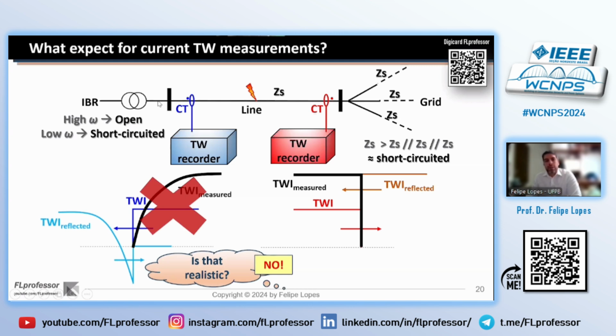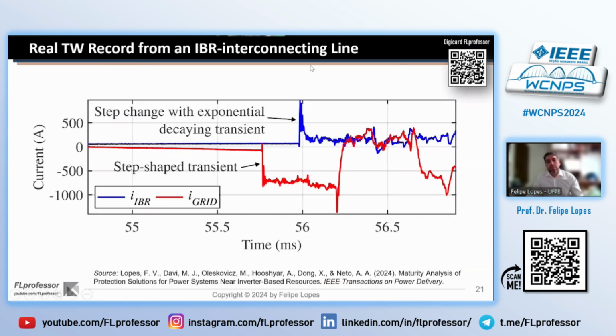higher frequencies, stray capacitances will show up in between the transformer windings and in between phase and ground here. So this is not a realistic analysis, and we can prove it by considering a real measurement of traveling waves in an IBR interconnecting line. This is a real measurement of transients considering a 1 megahertz sampling rate, and we can see that on the grid side there is a step-shaped transient as expected. But unlike this shape here, we see on the IBR side a very fast attempt at forming a step change, but which quickly decays with an exponential envelope.